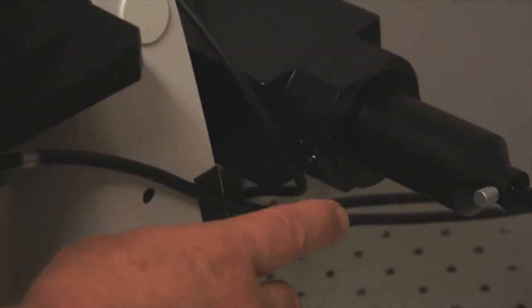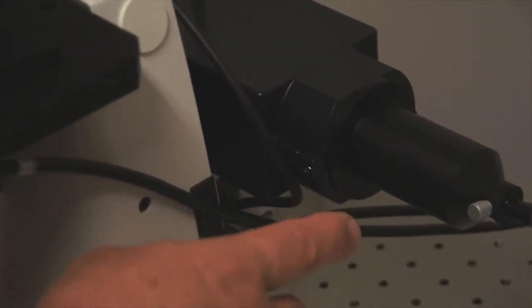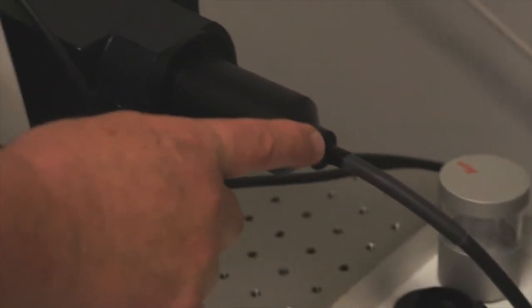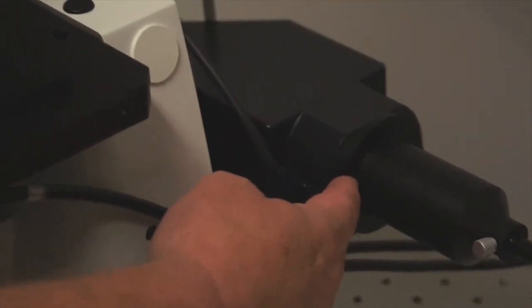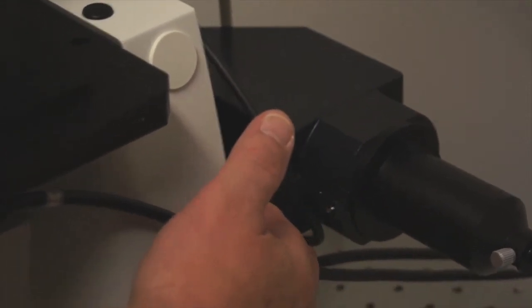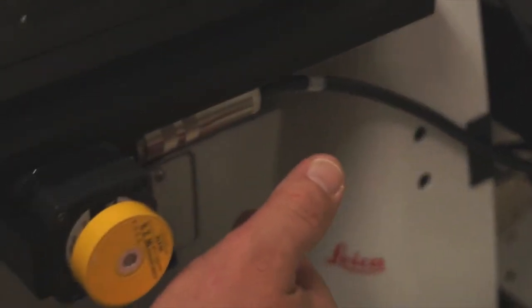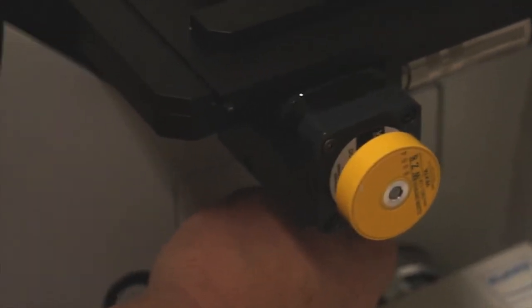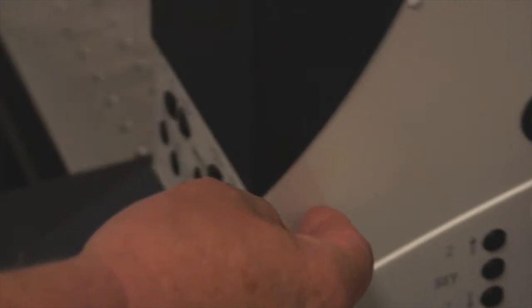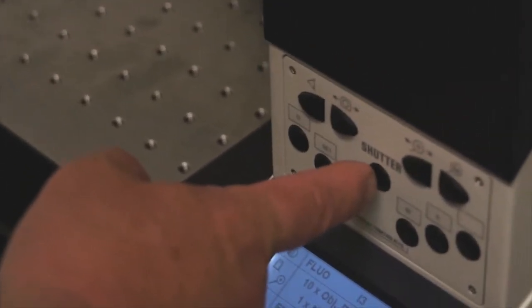Now that our illuminator for epifluorescence is turned on, we're directing light through the waveguide and into the epi-illuminator of the microscope. The light comes down through the body of the microscope, and it actually travels through a filter pack that's built into the body of the microscope. We have 4 filter packs in this microscope. The light travels through the filter pack and into the body of the microscope, and we can send that light to the specimen by pushing on the shutter button. And here you can now see that the light is illuminated on our specimen.